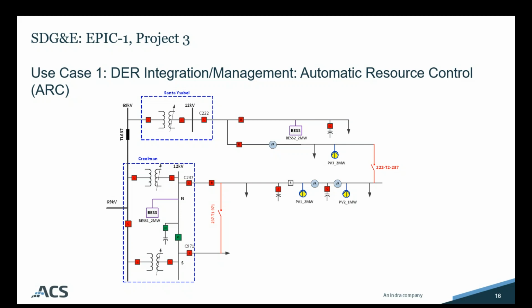So what they wanted to do is first compare how they're currently running these various devices, which is just from a local control based on conditions that those controls are seeing. So the voltages and currents that the voltage regulators, capacitors at the point of the system that they're at, they're just operating autonomously. They wanted to compare that to the ACS model-based distributed volt-var approach. And then they wanted to compare both of them and simulate one of these large PV tripping offline and see how each different method would react to that certain scenario.